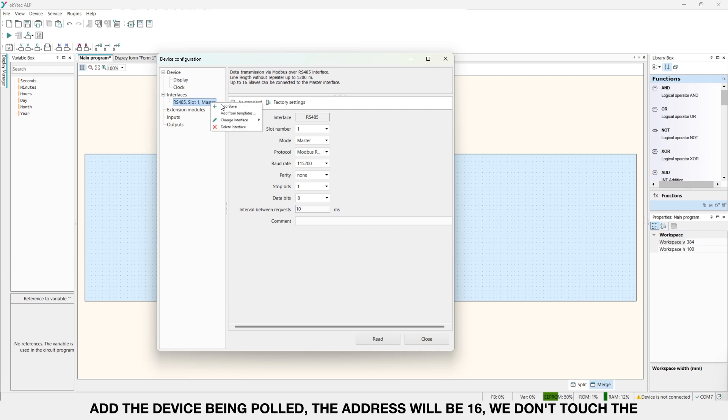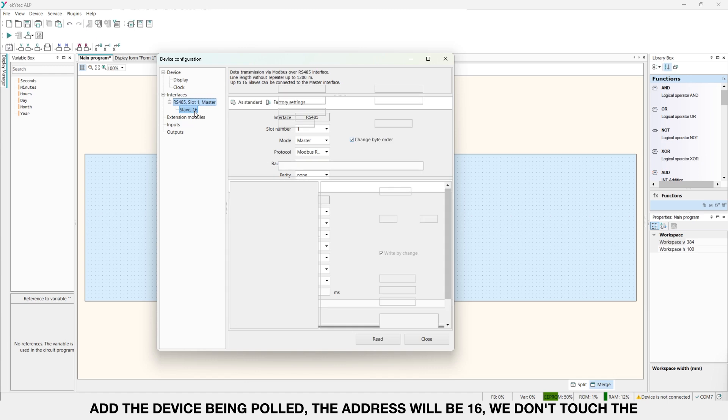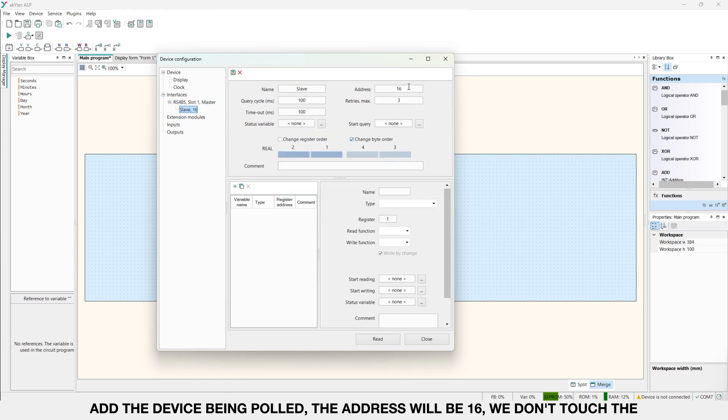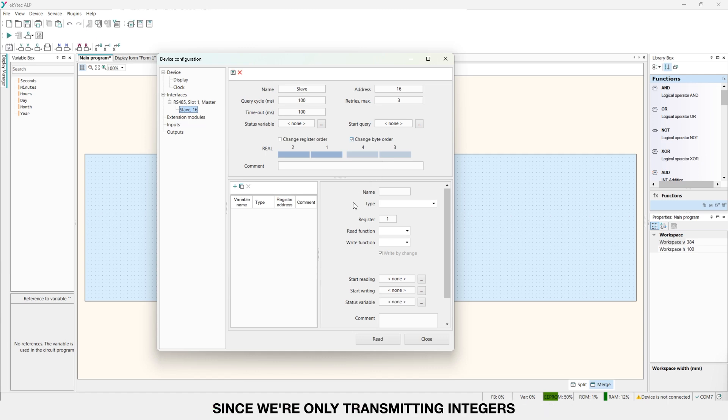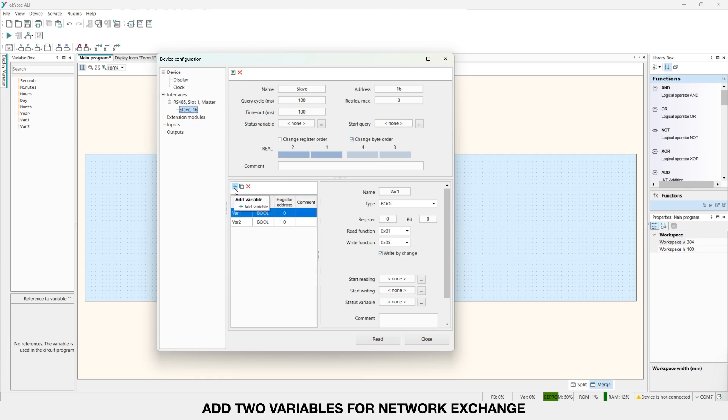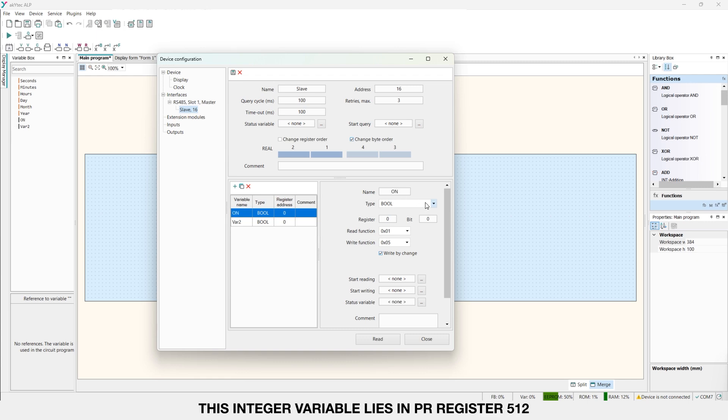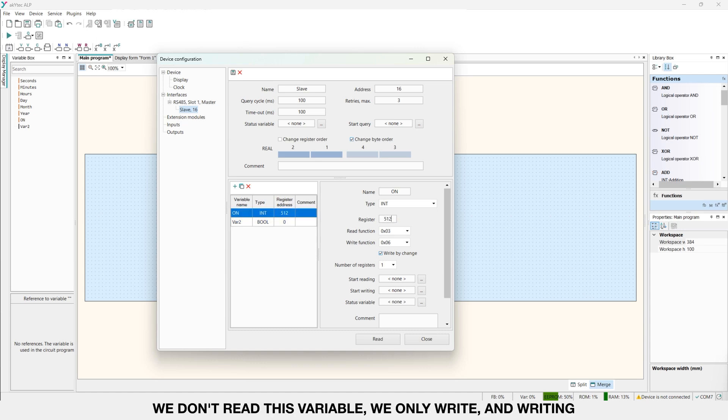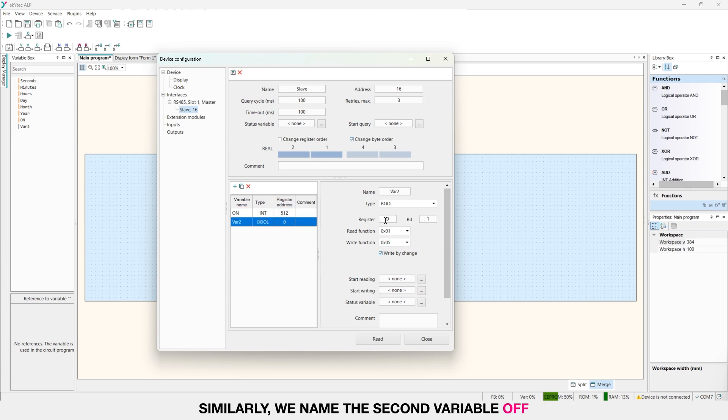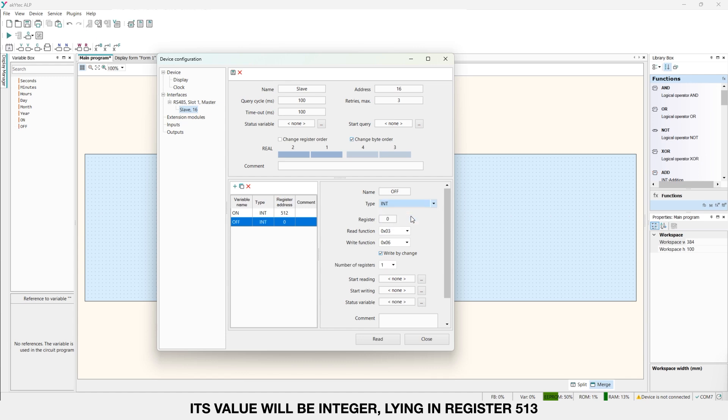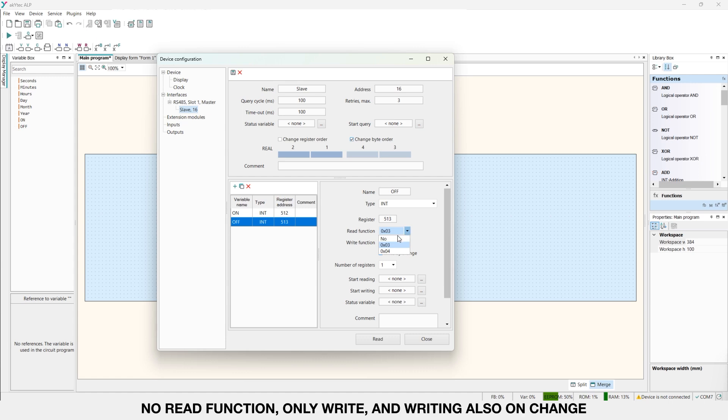Add the device being polled. The address will be 16. We don't touch the change register order and change byte order checkboxes since we are transmitting integers. Add two variables for network exchange. The first we will name on. This integer variable lies in PR register 512. We don't read this variable, we only write, and writing will be performed upon the change of the variable's value. Similarly, we name the second variable OFF. Its value will be integer, aligned in register 513. No read function, only write, and writing also on change.